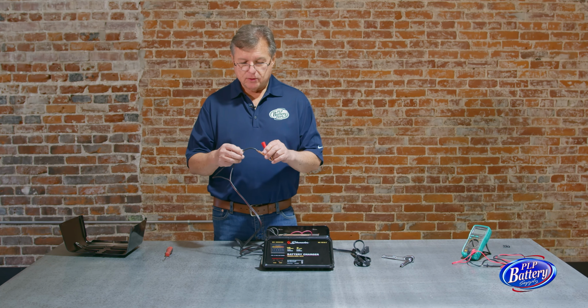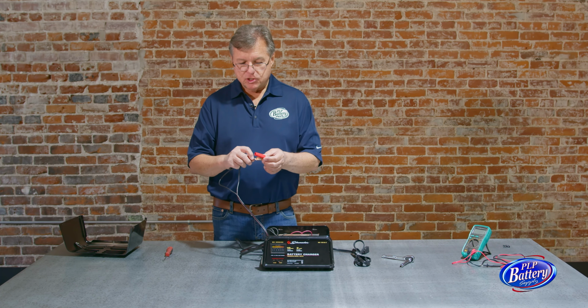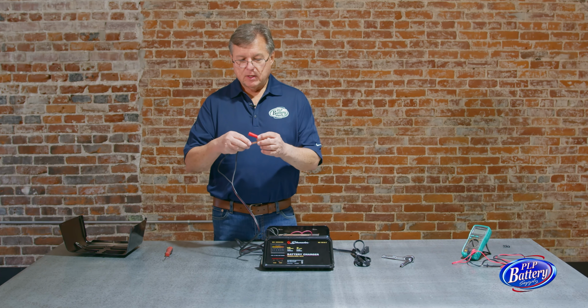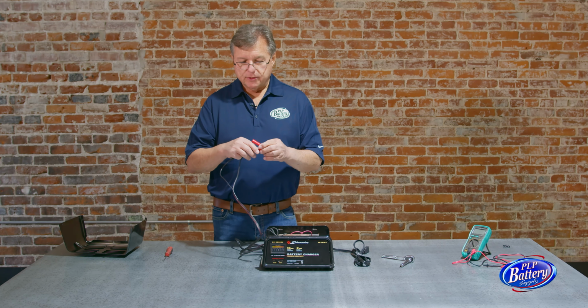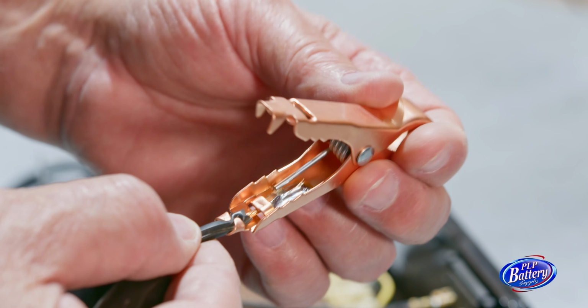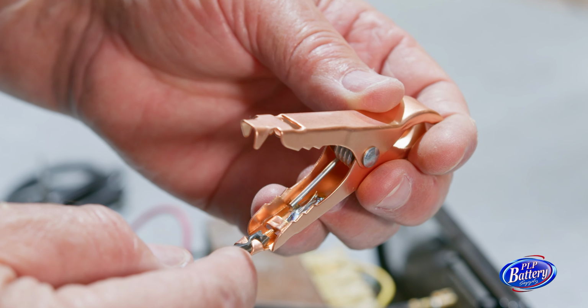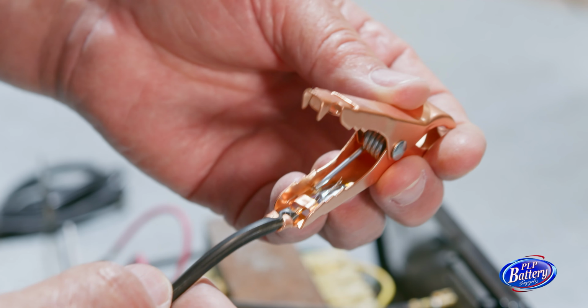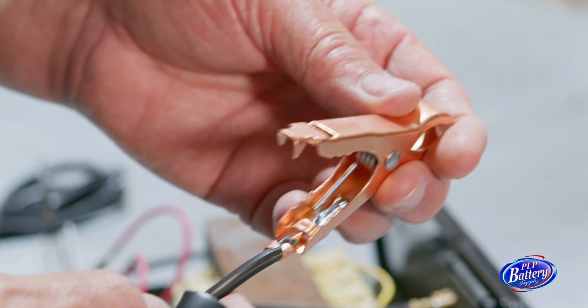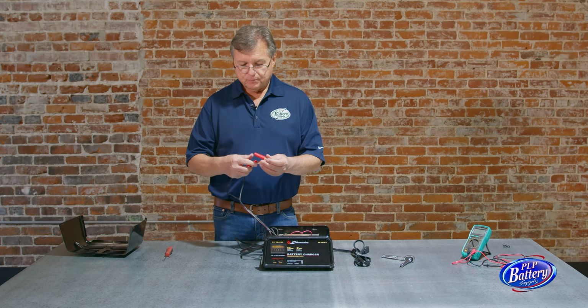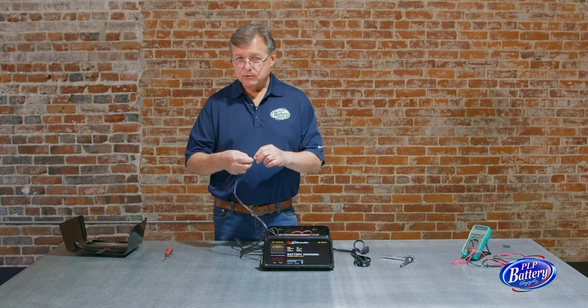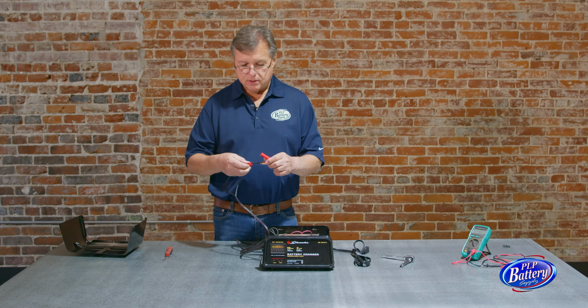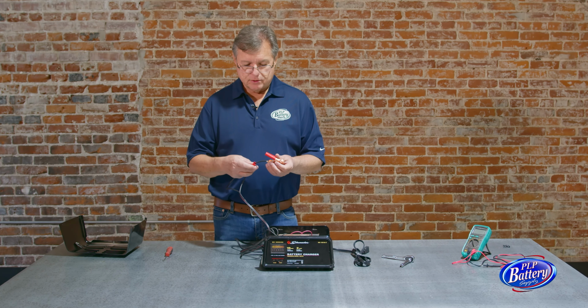Another way that these things will fail, and this can be for any of them, whether they're soldered or not, is they have an issue right where the wire comes out of the back of the little clamp, where the wire gets bent frequently and it breaks inside the insulation. So over time, you're liable to have a break inside the insulation that you don't see visually. You can feel it a lot of times, but you can't see it, and you don't know it unless you test it again with a continuity test. But if you can feel the break under the insulation, just clip it off, give away that couple inches and get down to where you've got clean copper in the wire and just put a new clamp on it.